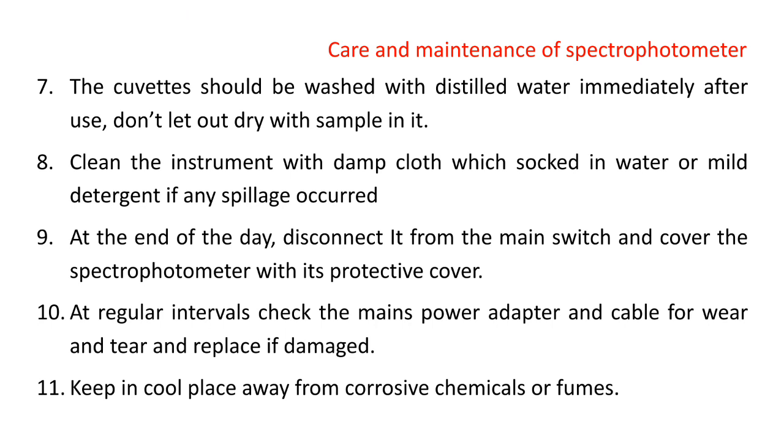Next, clean the instrument with a damp cloth soaked in water and mild detergent if any spillages occur. At the end of the day, disconnect the instrument from the main switch and cover the spectrophotometer with its protective cover. You also have to check the instrument at regular intervals. Check the main power adapter and cable for wear and tear and replace them if any damage has occurred. Also keep the instrument in a cool place away from corrosive chemicals or fumes.